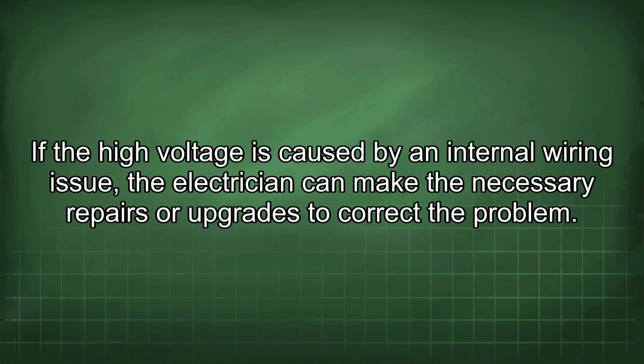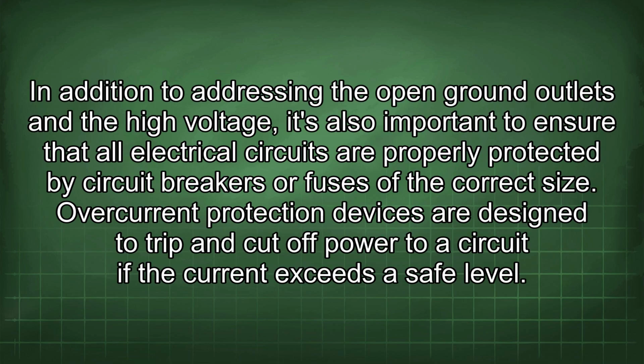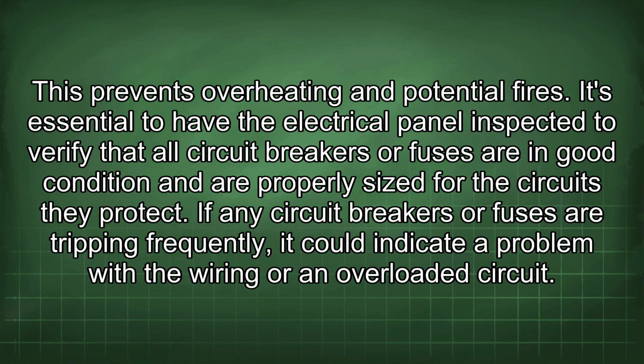If the high voltage is caused by an internal wiring issue, the electrician can make the necessary repairs or upgrades to correct the problem. In addition to addressing the open ground outlets and the high voltage, it's also important to ensure that all electrical circuits are properly protected by circuit breakers or fuses of the correct size. Overcurrent protection devices are designed to trip and cut off power to a circuit if the current exceeds a safe level. This prevents overheating and potential fires.